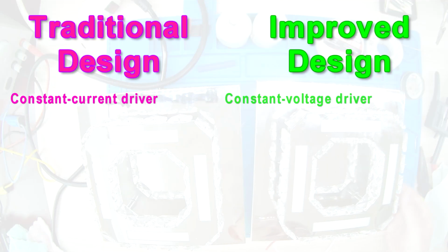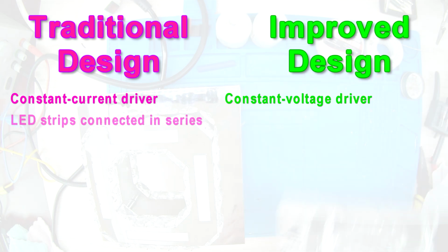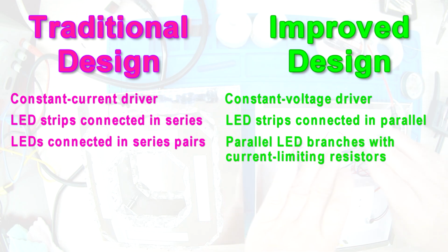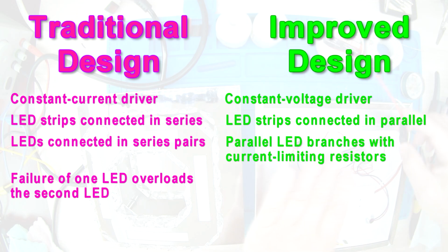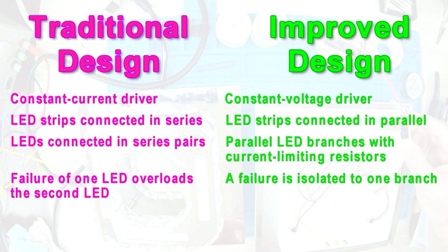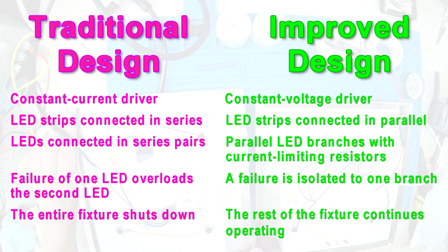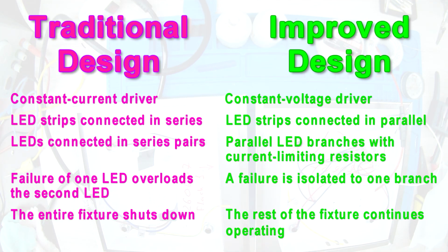The reliability of an LED light fixture depends not only on the quality of the LEDs themselves. The electrical circuit is just as important. By replacing a series-connected design with a parallel-connected design powered by a constant voltage driver, we eliminate one of the most common causes of complete fixture failure. Now, the failure of a single LED no longer causes the entire light fixture to stop working. That is what good engineering is all about.